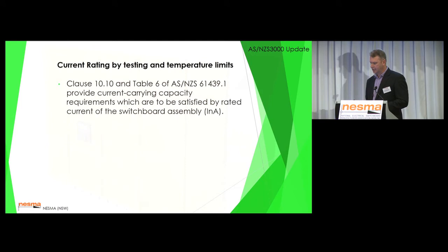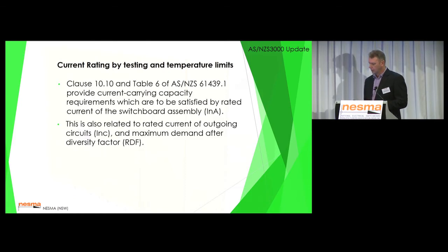Current rating by testing and temperature limits. So clause 10.10 and table 6, both in 61439, provide requirements which are to be satisfied for the current rating of a switchboard. This is also related to the current carrying capacity of outgoing circuit, so the INC, the maximum demand after rated diversity. So these are little things that you might see in specifications where a rated diversity is listed. This clarifies some of these in terms of calculations.